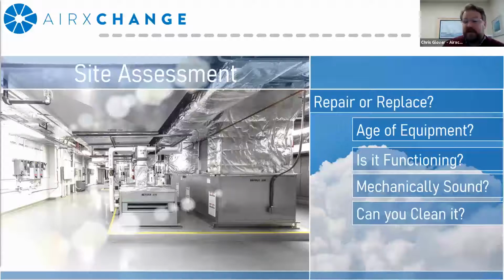Is the device mechanically sound? Are there any mechanical deficiencies like heat transfer medium missing, or significant rust or corrosion? Any visual bridging or gapping or media plugging that would minimize the airflow being delivered to the space. And lastly, if it's just dirty, can you physically clean it? Some devices are a little bit easier to clean than others, so that's something you should be asking yourself. The older the device gets, and the more no's you answer to these questions, the more likely you're going to be in a replacement versus a repair scenario.